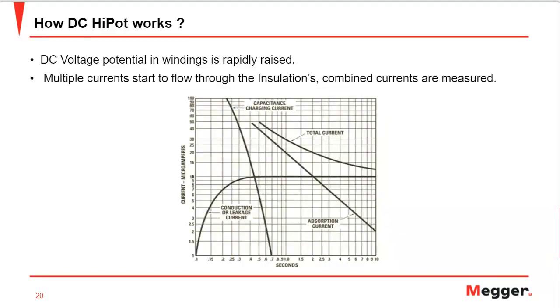Let's see how a DC high-pot works. We all know we ramp up the voltage, and then we measure the leakage current at a voltage higher than the terminal voltage or the rated voltage of the motor. Once the voltage is applied, there are multiple currents which start to flow on the insulation. The DC voltage is applied to open windings by the high-pot tester or the motor analyzer. The DC voltage potential in the windings is rapidly raised to the predetermined level, or raised in steps in case of a step DC voltage test. As this voltage is raised, several currents flow into and possibly out of the windings to the ground. The combined total of all these currents is what the high-pot tester calculates to give us the leakage current graph.